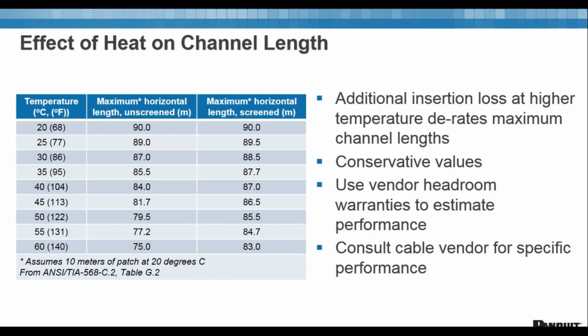Another comment here is that a lot of people see this and are somewhat concerned, saying this seems like a lot. This information has been in the C.2 document for as long as it's been out. Even though it's essentially new information people are not familiar with, it's been out there. It's affected 5E, 6, and 6A cables, and we have had no reported instances ever where this has come into concern. So just keep in mind that this guidance has always been there. Whether or not you're installing cable in a hot area, our own observation is that historically it hasn't been a problem. Going forward, our recommendation is that we might need to take this into account because the cables will be getting a little bit warmer.